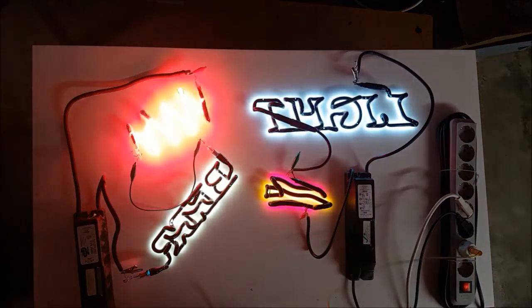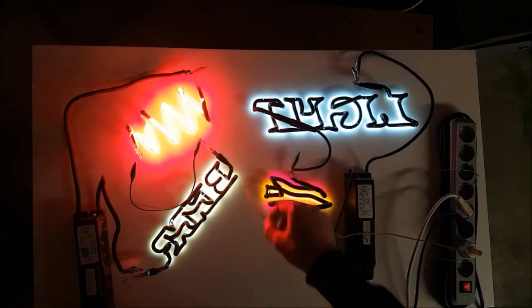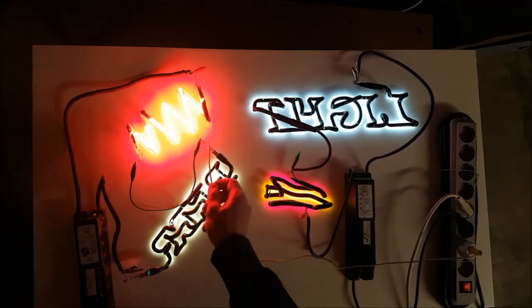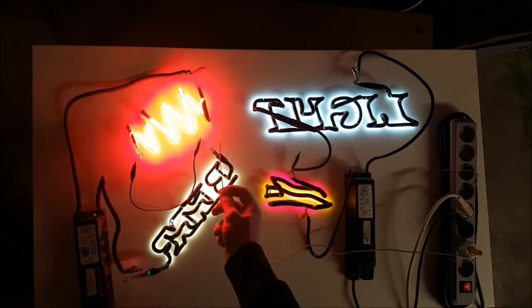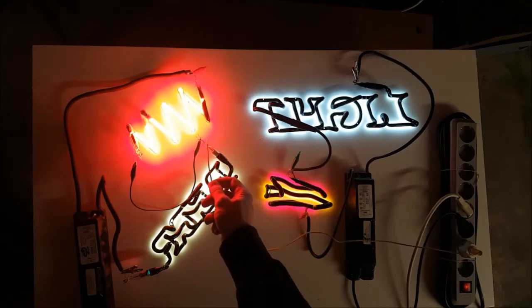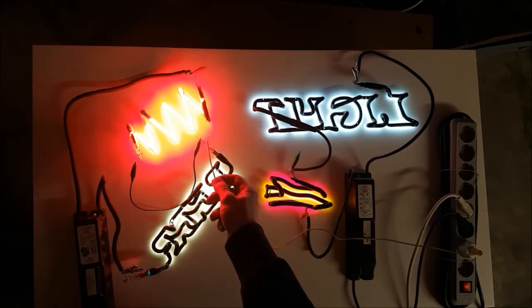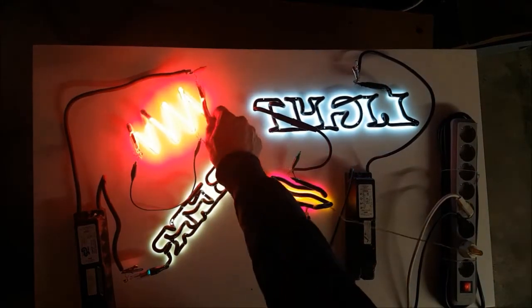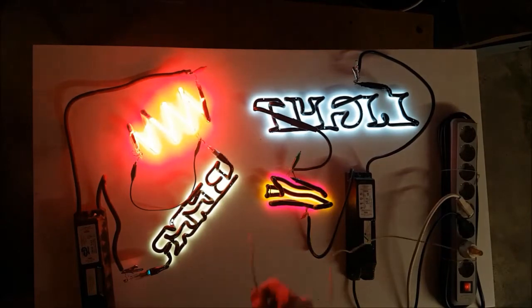The thing that's normal and that can occur is when the high voltage spans across all the tubing here, and when the ground fault or the open circuit is about in the middle of the secondary circuit, then the transformer in some cases cannot detect it. That is normal. It's just a physical limit of how the detection works. But anyway, something's wrong with this transformer because this end did not detect the ground fault, and I'll show you that it also doesn't detect the open circuit.